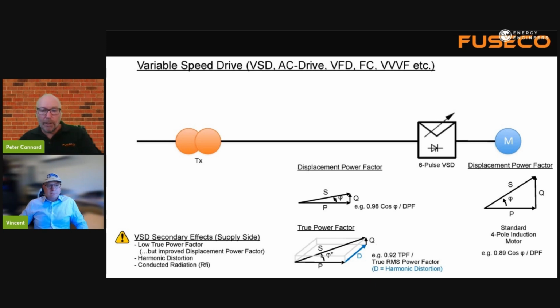The closer we get to 1, the better, the closer it is to a resistive load. But you can see down the bottom here, 0.92. That's typical true power factor for a 6-pulse variable speed drive, the most common motor starter, motor controller in the industry today. Next slide.